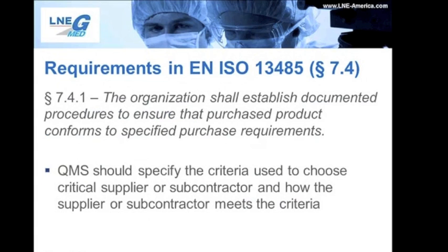So let's take a look at some of the pertinent clauses in Section 7.4. First, Section 7.4.1 states that the organization shall establish documented procedures to ensure that purchased product conforms to specified purchase requirements. In other words, a manufacturer should determine how they would choose their critical subcontractor, the criteria they would need to consider in order to make sure their product conforms, and set up procedures to ensure that the product or service they receive actually conforms to what they need in the first place.